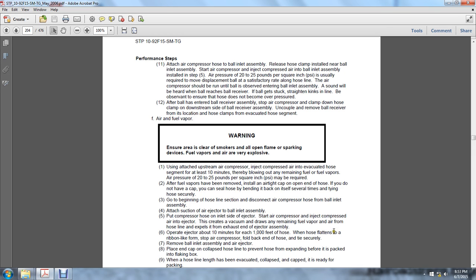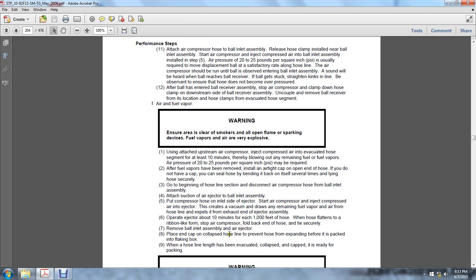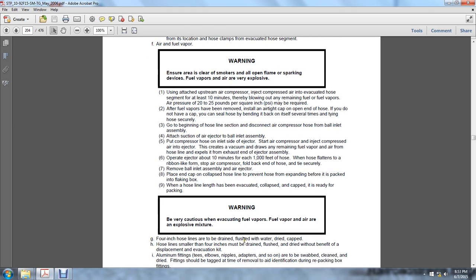When the hose flattens to a ribbon-like form, stop the air compressor, fold back the end of the hose, and tie securely. Remove the ball inlet assembly and air ejector. Place an end cap on the collapsed hose line to prevent the hose line from expanding before it is packed into the flaking box. When the hose line length has been evacuated, collapsed, and capped, it is ready for packing. Warning: be very cautious when evacuating fuel vapors. Fuel vapor and air are explosive mixtures.